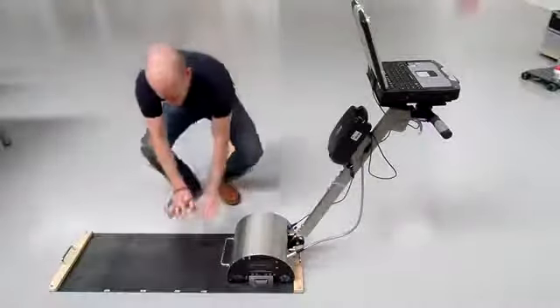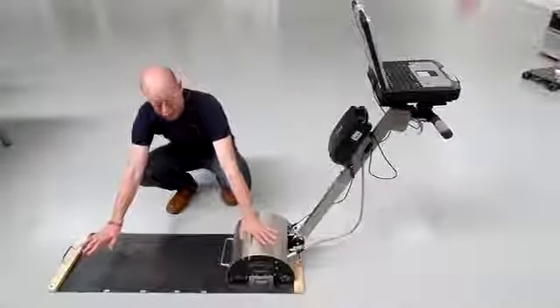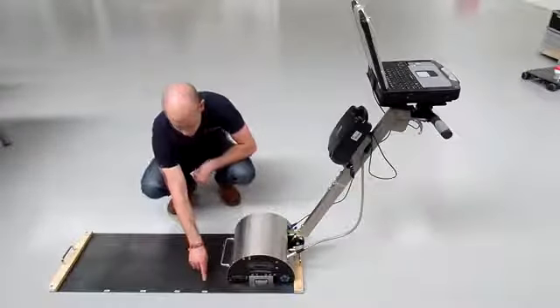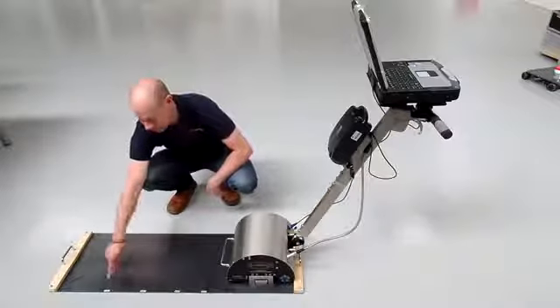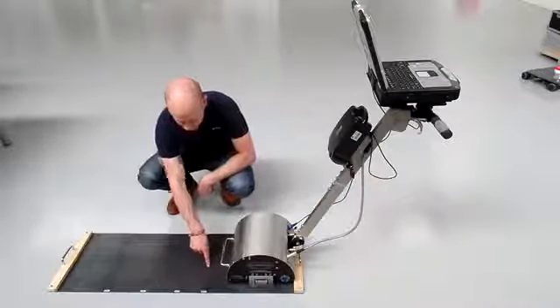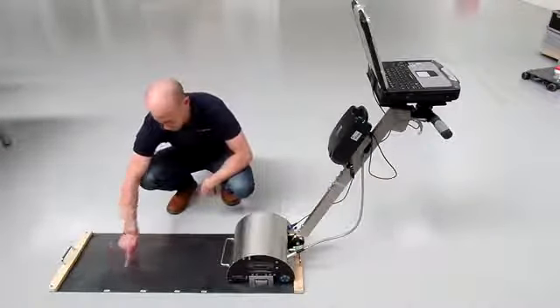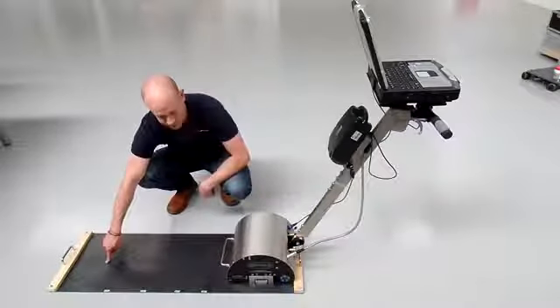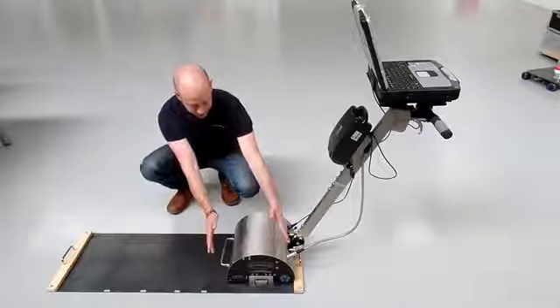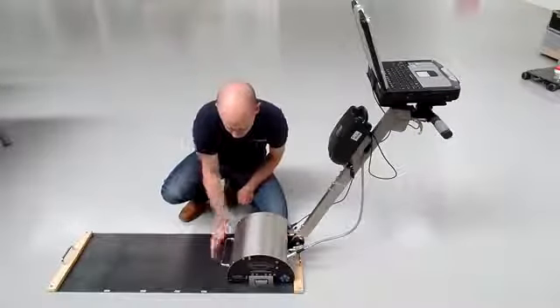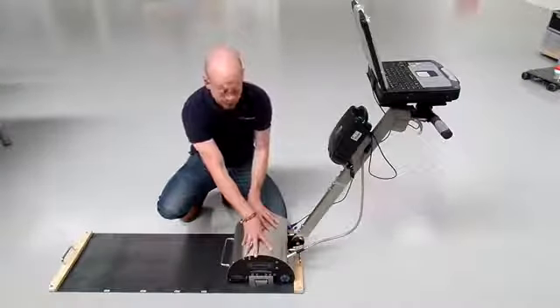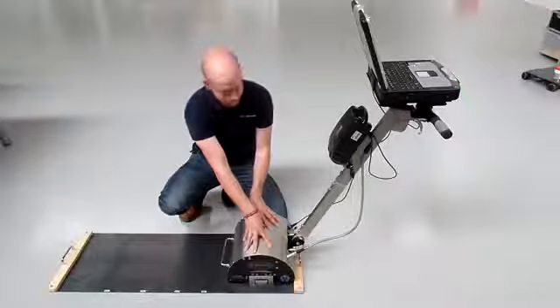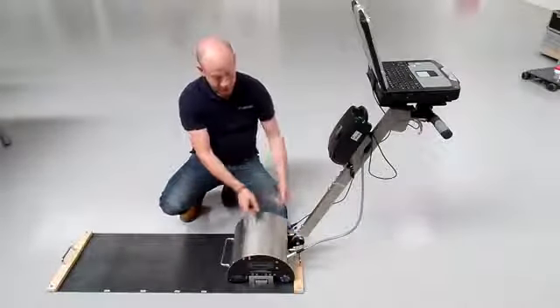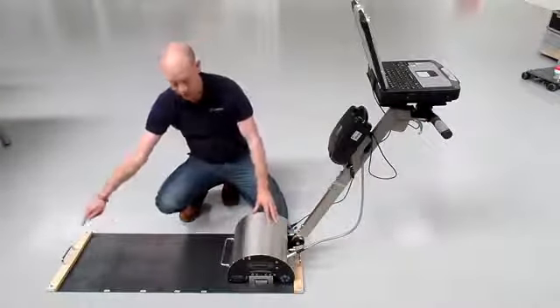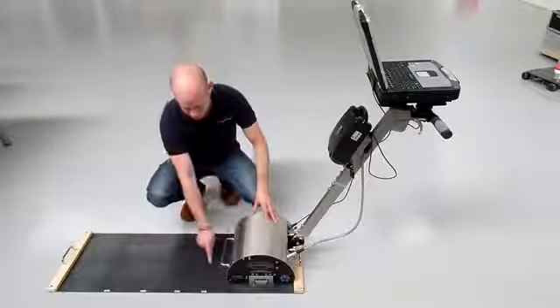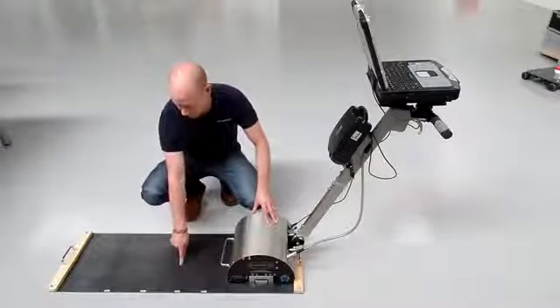Calibration plate is a nominal 6, 8, 10 or 12 millimeter thickness with 20%, 40%, 60% and 80% through wall indicators in the rear of the plate at approximately these positions in the center. On the right hand side of the plate there is an area of nominal plate thickness where the TruFlux unit must be positioned to start a calibration. We're going to do the calibration in this direction from right to left. The unit will look to see the 20% indication first.